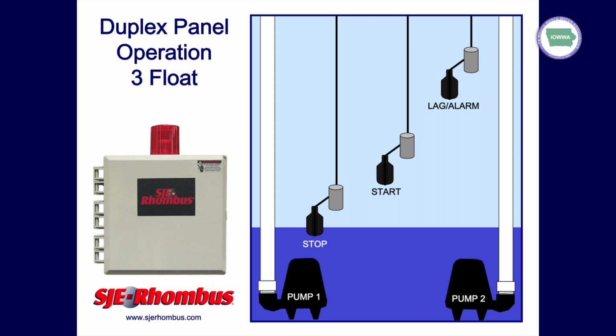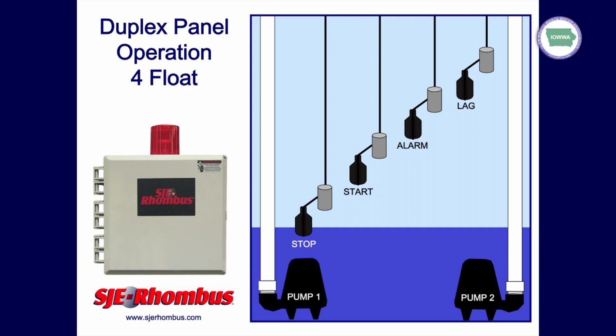So anyways, we also have the ability to separate the lag and the alarm function by going with a 4th float. So we'll talk about that. This is one of the areas where I find a lot of misunderstandings out there. When you have a 4th float that separates the lag function from the alarm function, what level should they all be mounted at? This would be my preference, and we may have people out there that argue with me on this point. I'm pretty confident that my position's correct, and I'm happy to talk about it if anybody feels differently. But I'll tell you the theory behind why I feel it needs to be the way it is here.